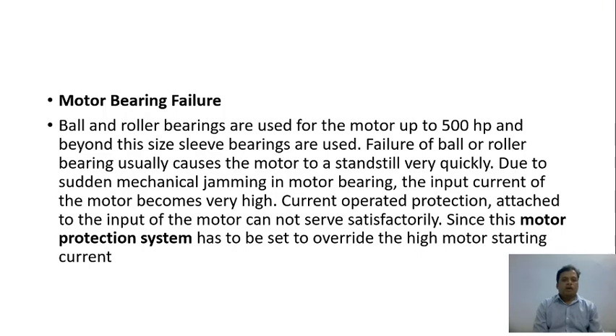As the motor bearing failure happens, more current is drawn and it may cause damage to the synchronous motor. This type of motor bearing failure can also happen in the induction motor. So we will discuss the next thing: what protection is to be provided against which fault to have smooth operation of the synchronous motor.